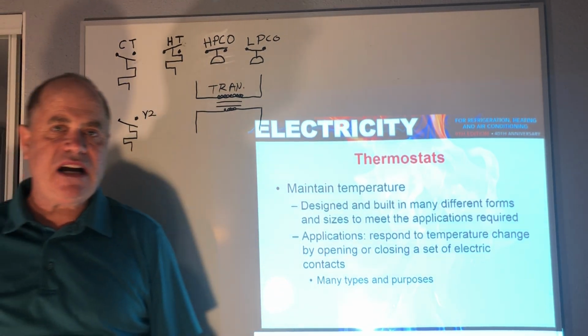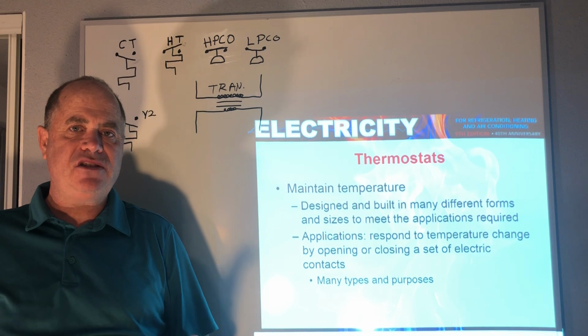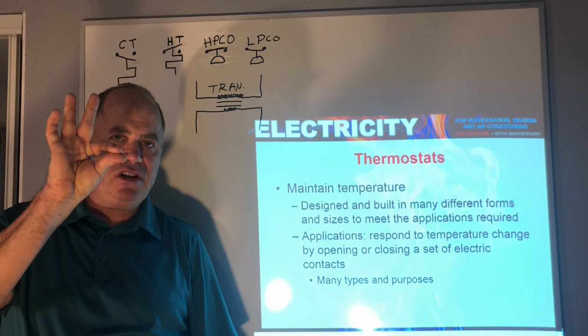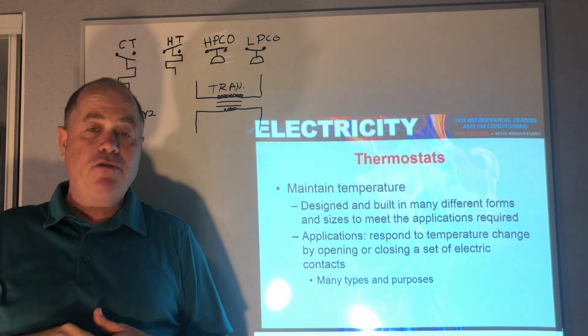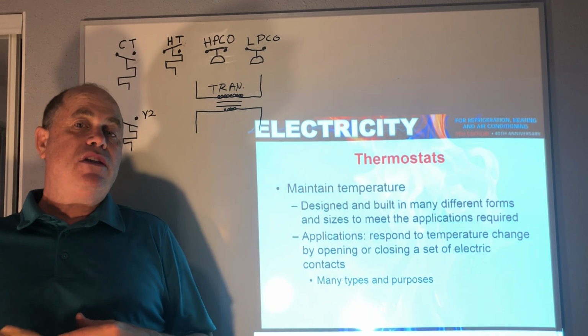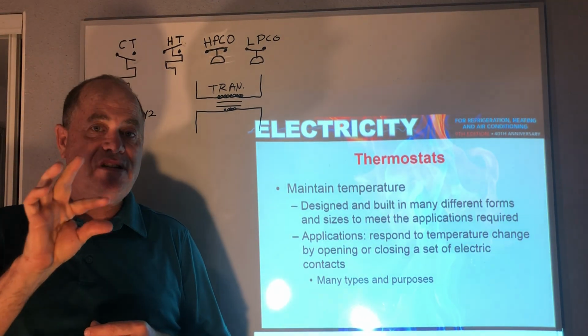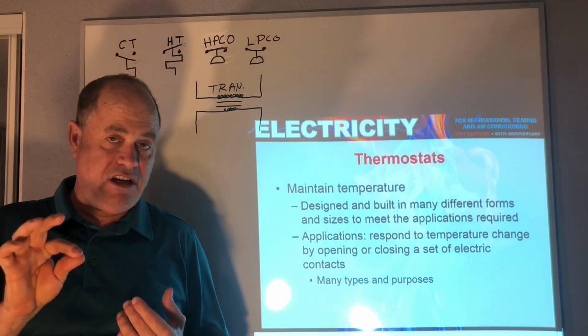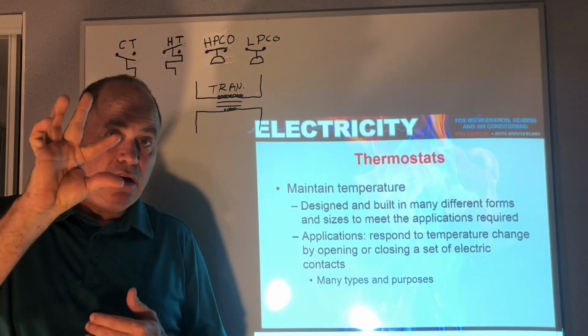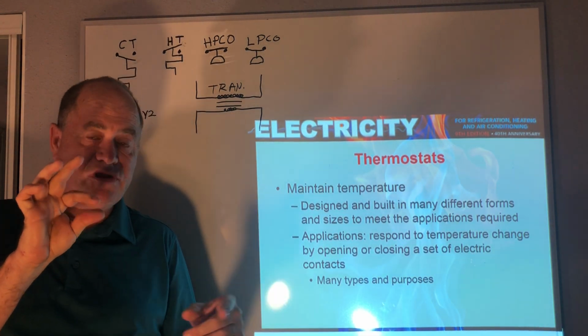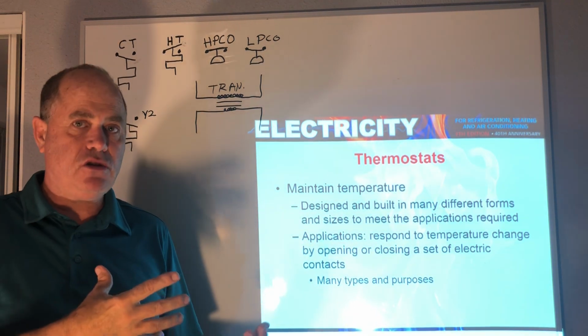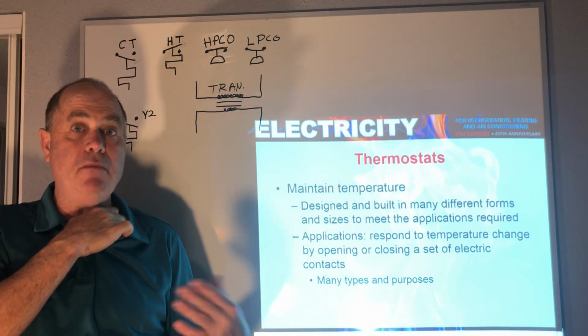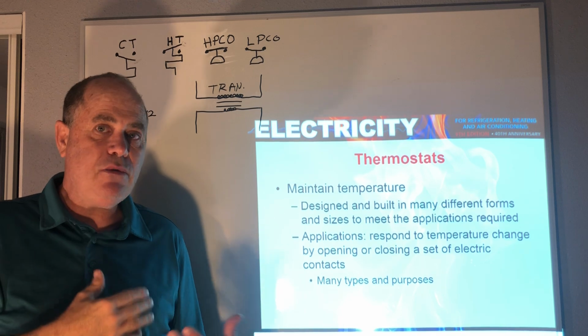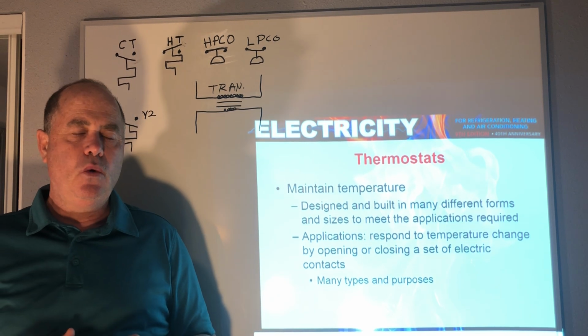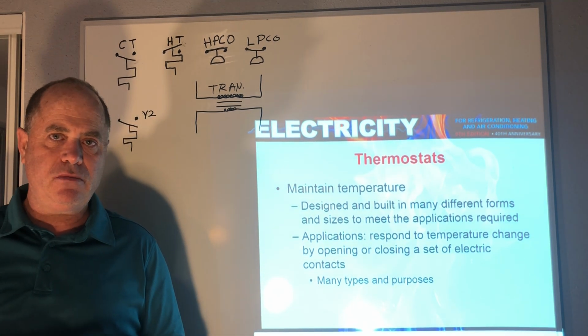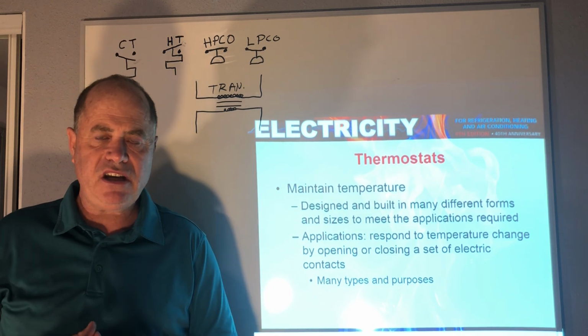Okay, thermostats. Generally the basic concept is that we open and close a set of contacts. For a cooling thermostat, when the contacts close, it's like the thermostat saying, hey, it's too warm in here, we need cooling, let's close and send an electrical signal so that a refrigeration compressor can come on, either directly with a line voltage thermostat or indirectly with a low voltage thermostat and the use of, let's say, a contactor.